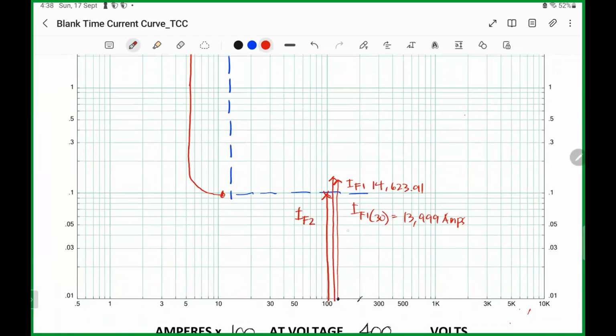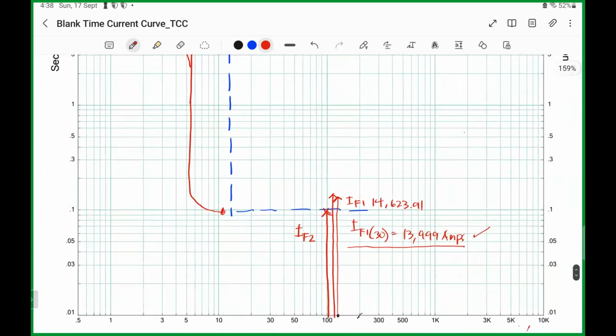So this will be my setting of my protection. Okay? So this is the reference as a minimum fault that I calculated at 30 cycles. This is my reference. Now, if you still have feeders on the main bus, definitely your instantaneous will be disabled to give way to the downstream circuit breaker to operate. They cannot operate at the same time. If you have a fault in feeder 1, your main circuit breaker, your transformer protection or secondary protection, cannot trip together with it. So I assume this one, 13,999, is based on the short time pickup, instantaneous disabled.